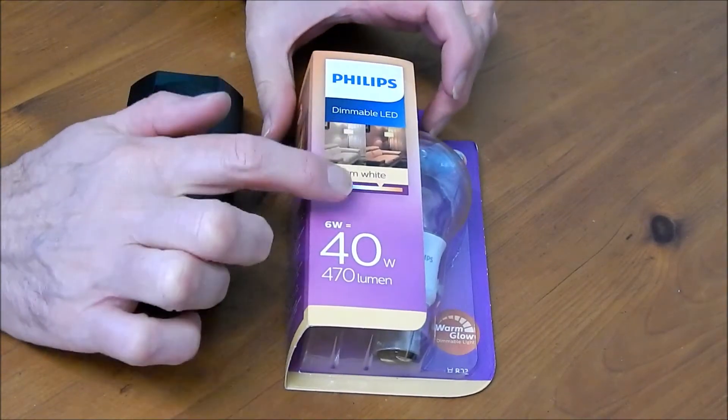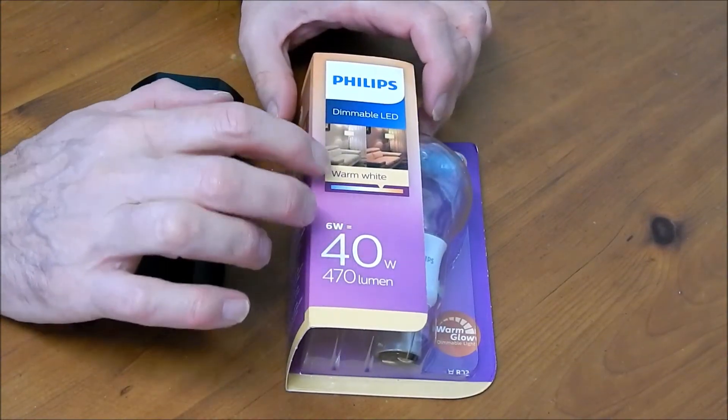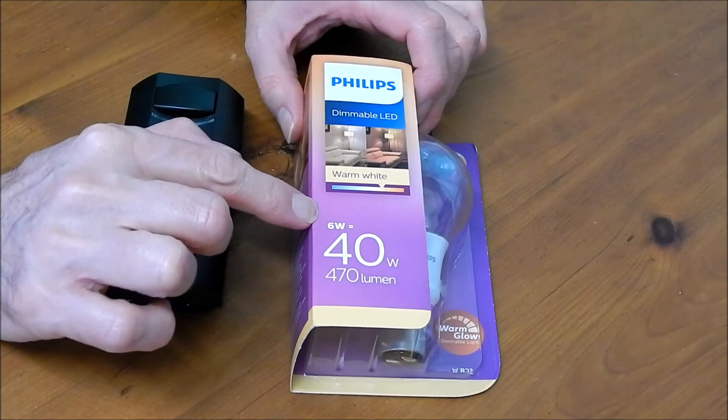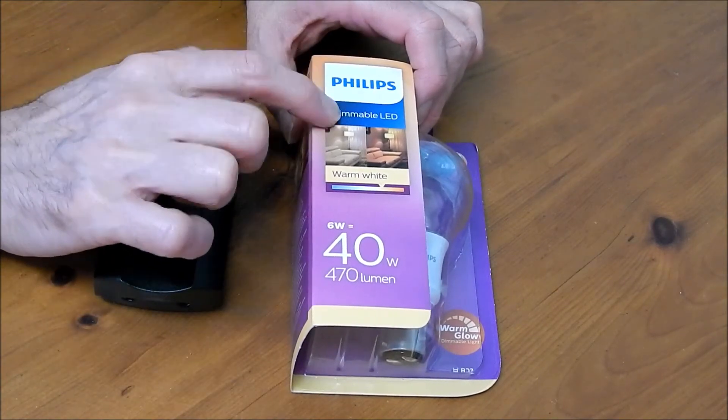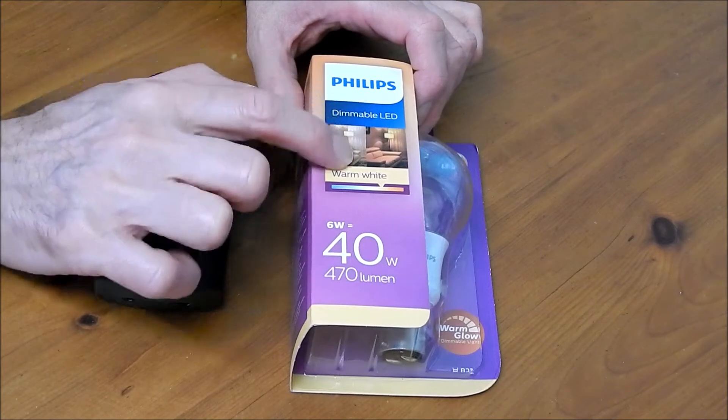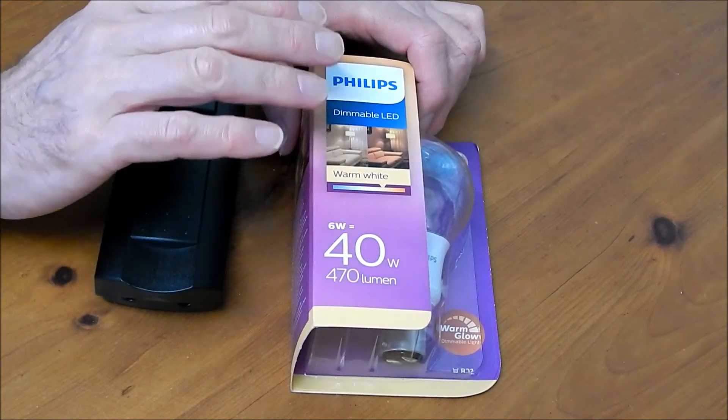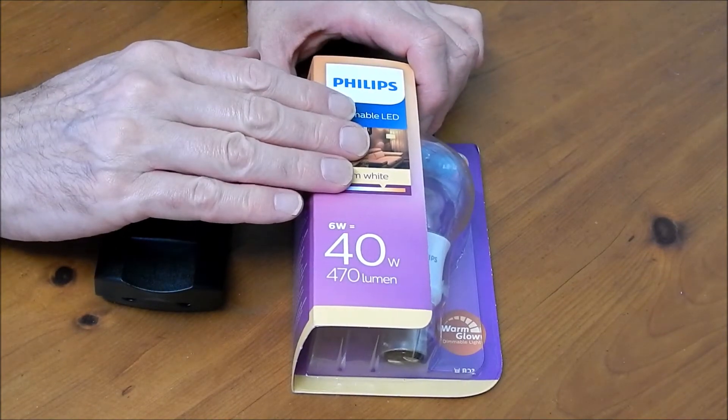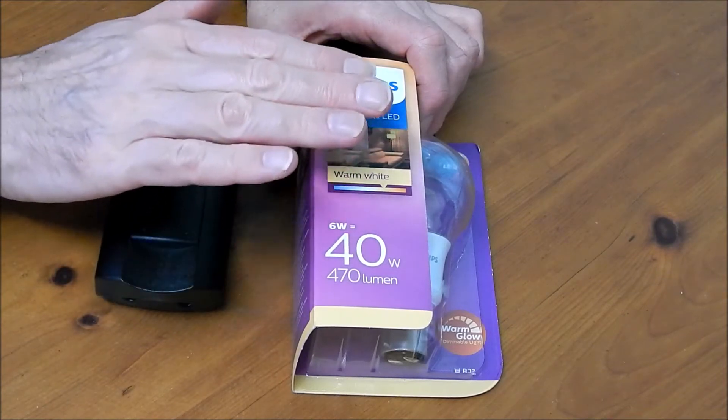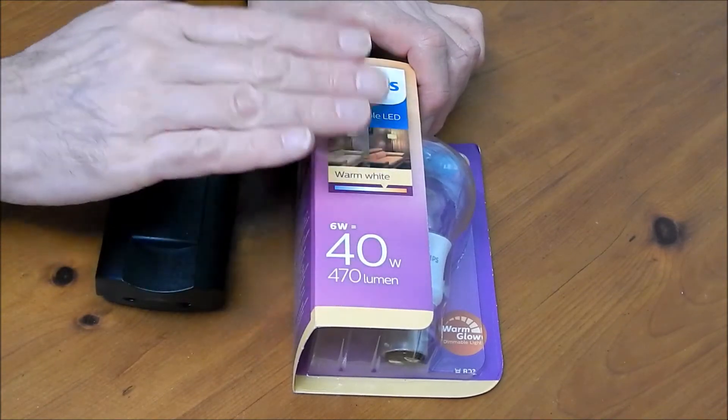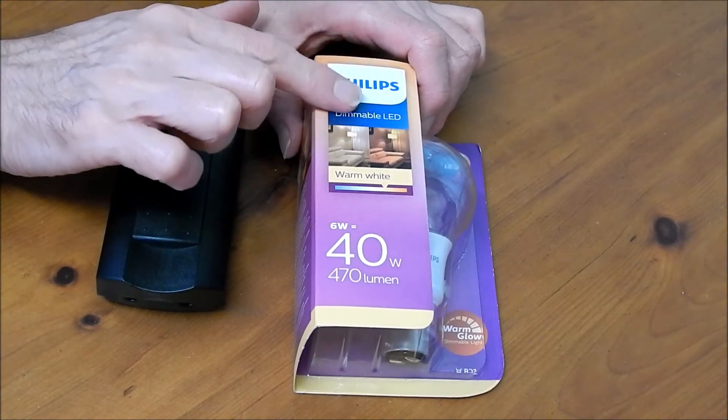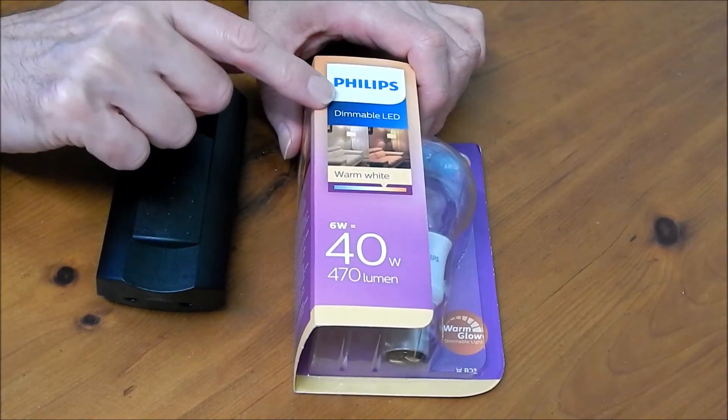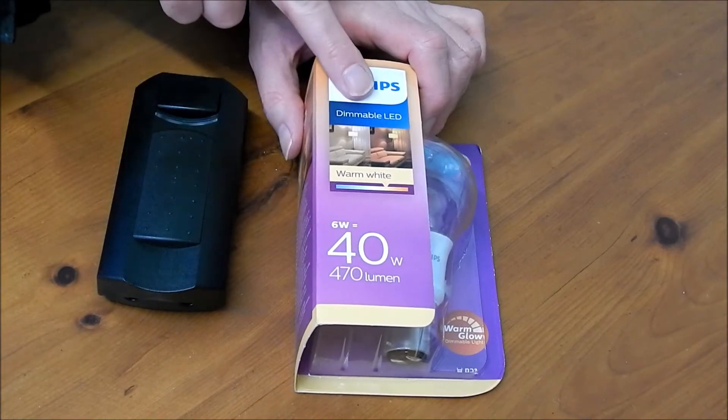Most important thing to remember is if you're converting a light fitting nowadays to a dimming one, make sure that you use a dimmable lamp or bulb in there. Most of them are not dimmable and obviously now being LED there's a lot of electronics in there and the mains power is going to get disrupted when you put it through a dimmer. So absolutely the first thing you need to do is make sure this one is dimmable. I've done that.